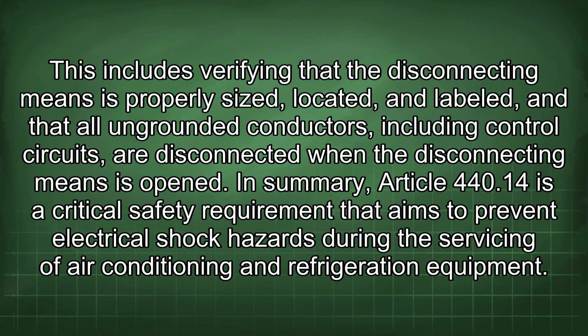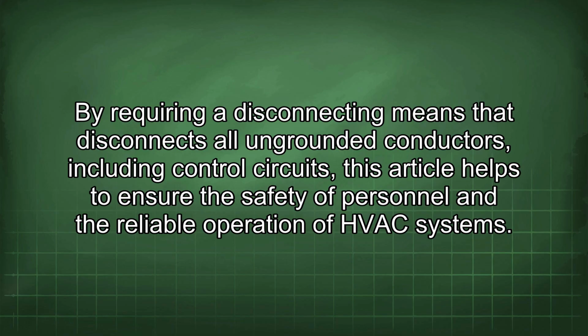In summary, Article 440.14 is a critical safety requirement that aims to prevent electrical shock hazards during the servicing of air conditioning and refrigeration equipment. By requiring a disconnecting means that disconnects all ungrounded conductors, including control circuits, this article helps to ensure the safety of personnel and the reliable operation of HVAC systems.